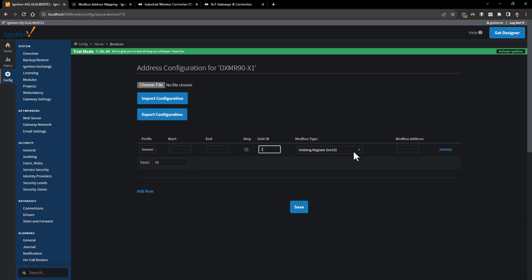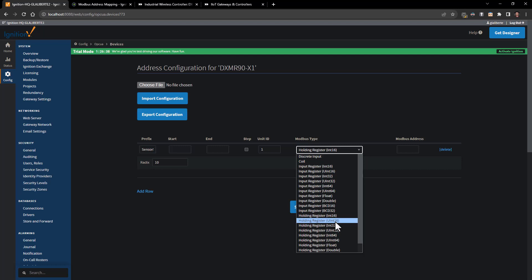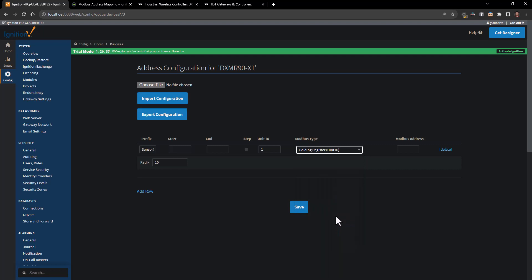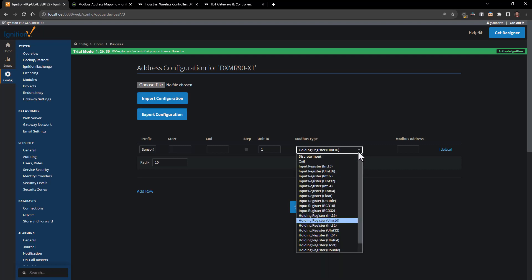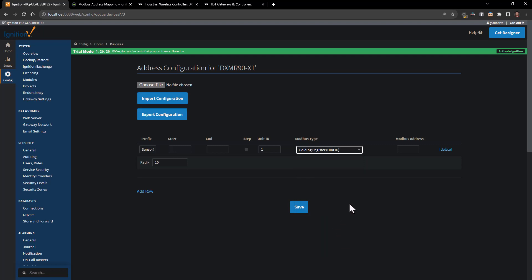For our data coming in, typically most of our stuff is going to be an unsigned integer. If you do have a signed device or you have some signed information, you can pick just standard integer. You saw there's a number of choices - for the most part our system is either going to be unsigned 16, signed 16, or float. We do have some floating registers.